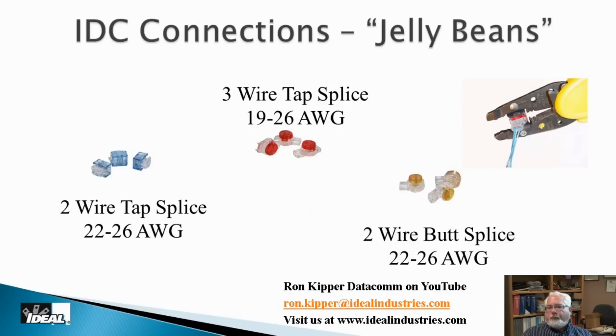So what the red ones do for me is they tap a line. Basically I would take one of those conductors I want to tap, I'd cut the cable, take those 2 ends and put them inside of a red one. And the red ones have a hole for a third conductor, which would be tapping off to that phone I'm going to feed. And when I crunch it down with a pair of pliers, it'll make all 3 connections, again using those IDC connections. We sell a plier, and everybody else has got a plier, and a pair of channel locks will probably work fine as long as you don't crush the little plastic housing of the jelly bean. Now, the yellow ones, what they were designed for is splicing only.